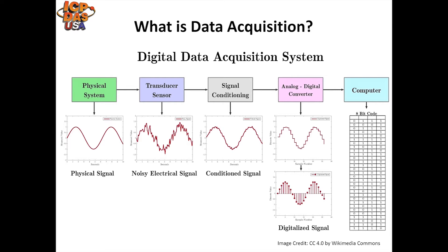The components of data acquisition systems include: sensors to convert physical parameters to electrical signals; signal conditioning circuitry to convert sensor signals into a form that can be converted to digital values; and analog-to-digital converters to convert conditioned sensor signals to digital values. A data acquisition module is any device designed to collect field sensor data — it's an intermediary device between you and the sensors. Most sensors output data in a raw format that can't be read by a PC or tablet, so the DAQ module takes that sensor data and presents it in a format that can be understood by your PC or controller.